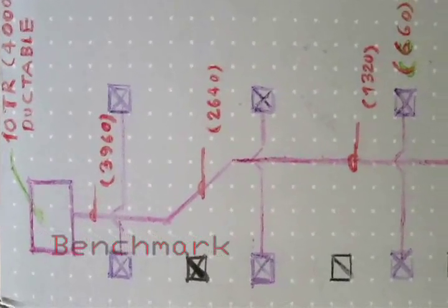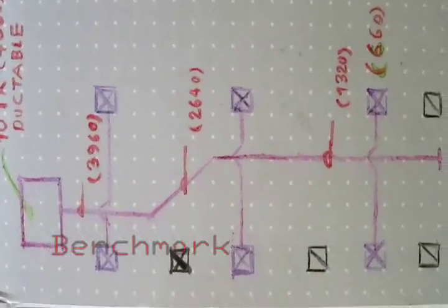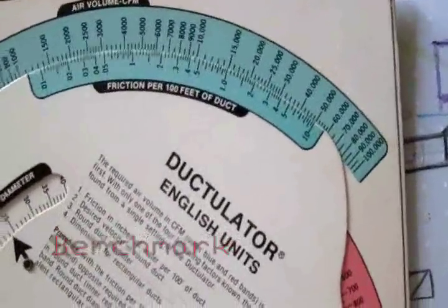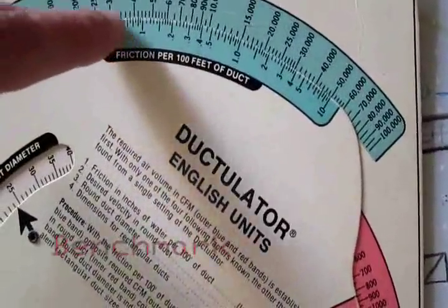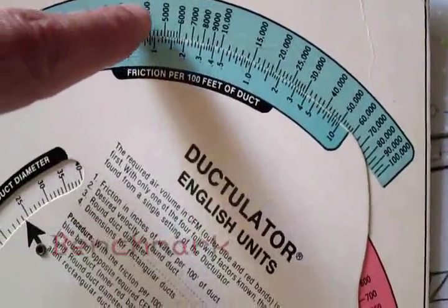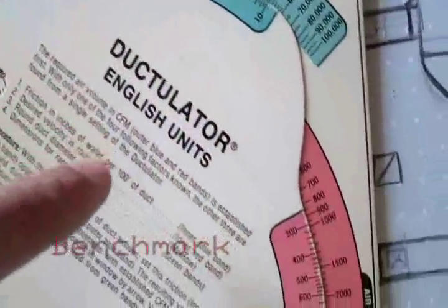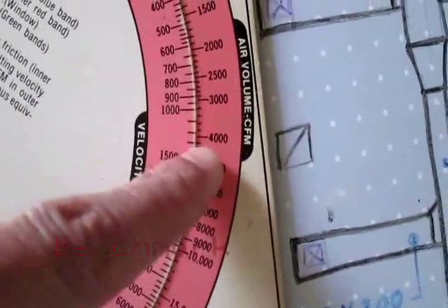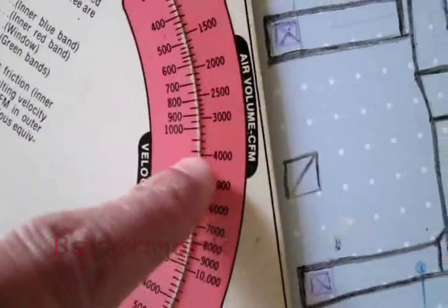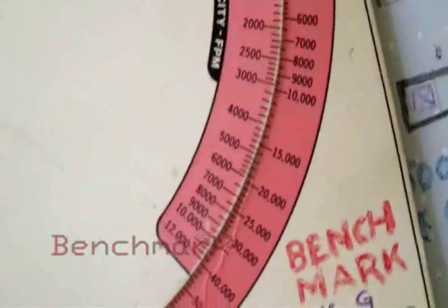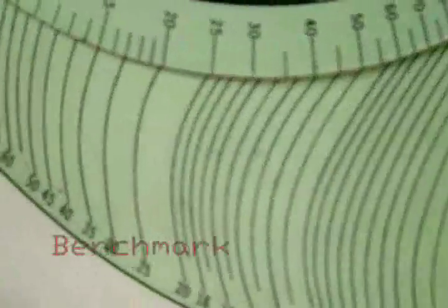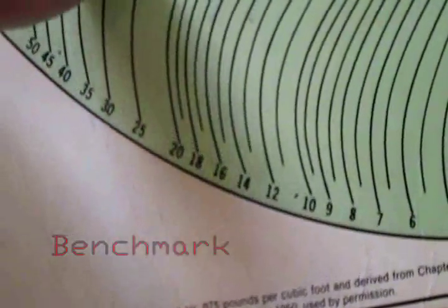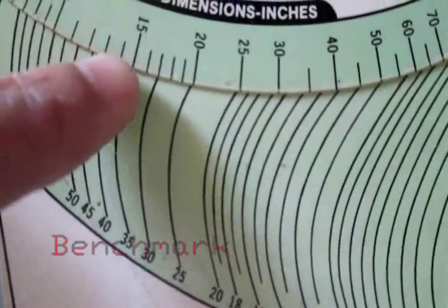For this we have to do calculations, which we have already done. We will start by using the ductulator for the sizes. The first value is 4000 CFM, and we are getting a 500mm duct size between the false ceiling and the slab. We are starting with 0.1 friction with 4000 CFM.